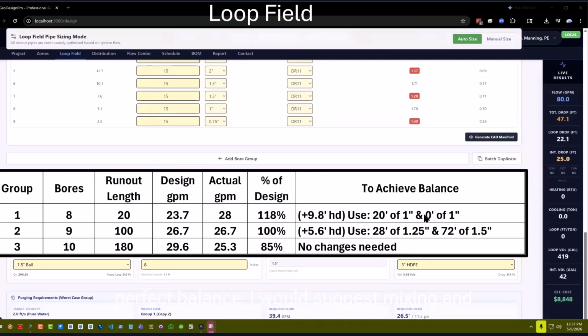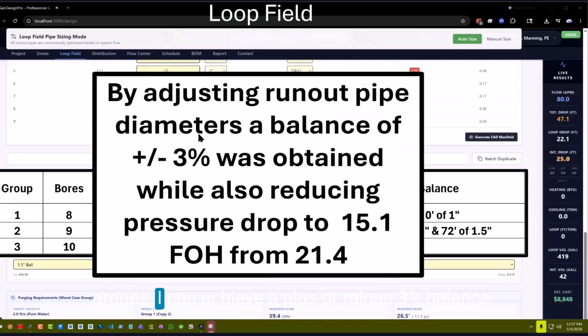So I challenge the need to have perfect balance, but to satisfy those engineers who want perfect balance, I would suggest mixing and matching different diameters in the runout pipe. You end up putting smaller pipe in the closest group. You're building an extra 9.8 feet of pressure drop in that runout pipe, or 5.6 feet of head in that middle group. Instead of reducing pipe sizes on those closer groups, I'm going to increase the pipe size going out to the third group. So when I bump that up to 3-inch from 2-inch and make minor tweaks on the other groups, I can achieve a plus or minus 3% balance.